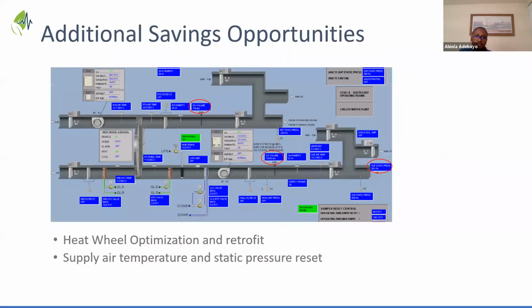Awesome. As we talked about, there are some additional savings around optimization, because one of the things we noticed within all of these projects is figuring out the right way to do this the first time. One of the things we talked about is optimizing the heat wheel operation. In a lot of hospitals, especially around these operating room air handling units, it becomes critical, and this is something you are currently working on. Also, optimizing the supply static pressure resets is another opportunity that we are seeing in a lot of the current hospitals.